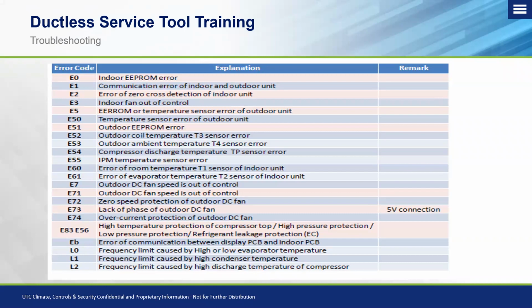So you want to make sure if you're reading the code on the tool that you use the tool's error code list to make sure that it matches up and confirm what that code is trying to tell you. Now, for example, codes that stay the same throughout would be an E1 code. We know an E1 code on the indoor unit is a communication issue. Well, on the tool, it's also a communication issue. But the biggest thing is making sure you're using this error code list, if you have an error code on your tool, to get the correct diagnosis of what's going on with the system so that you're not chasing a ghost code.